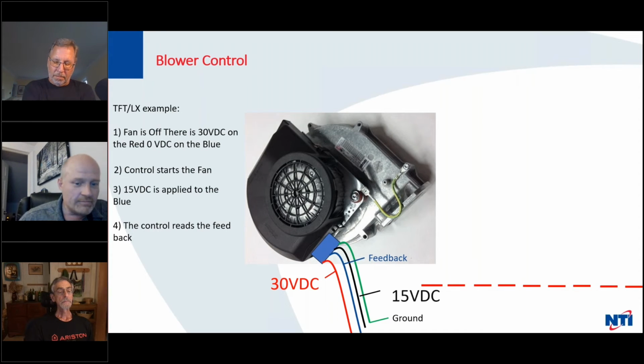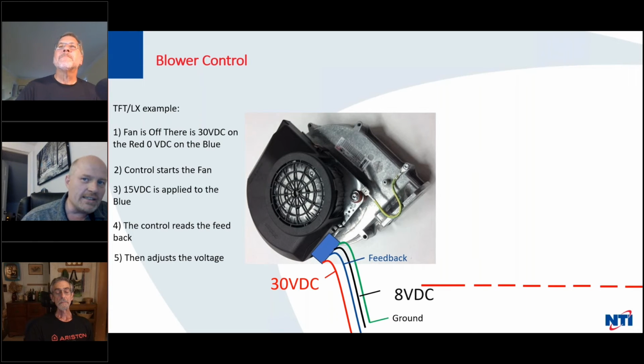basically it would apply less or more voltage to get that pulse to where it wants to see it. So our controller adjusts the voltage up and down. So we go to 28 and then to 8 volts DC. And after we go to 8 volts, you can see that the pulses are much slower, indicating a much lower speed coming from the blower. So that's how your blower works. The colors of these wires are going to vary. The feedback wire, your voltmeters just aren't equipped to read it. If you do happen to have an oscilloscope, you actually could hook it up and you could get a reading from that. For the rest of us, which is like 99%. Yeah, no, these days though, you can get a pretty cheap one for your phone.